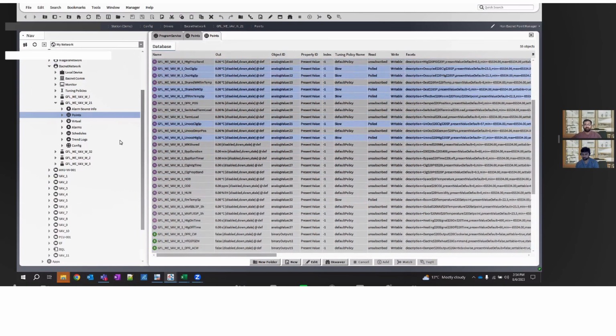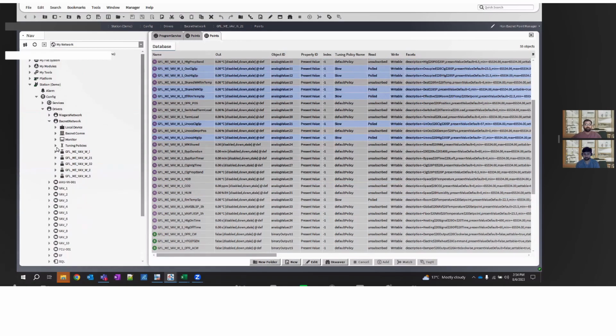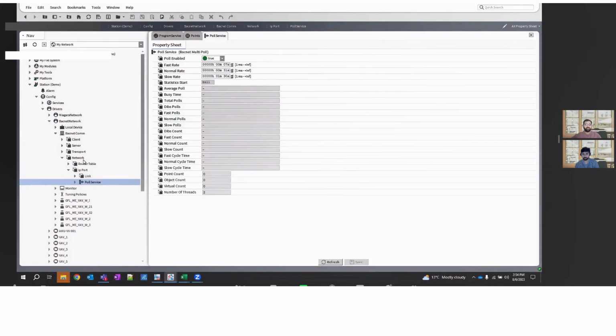When on site, to determine how your system is performing, you can go to BACnet network. If it's an IP port, go to IP port poll service. If it's an MSTP port, then go to MSTP poll service, and you will see the busy time here, normal polls, and all that data, fast cycle time, and overall how much we are consuming. If the busy time is more, that means your system needs to slow down. Generally, I try to keep it to 15 to 20%, which is also on a higher side. It should be even further lower.